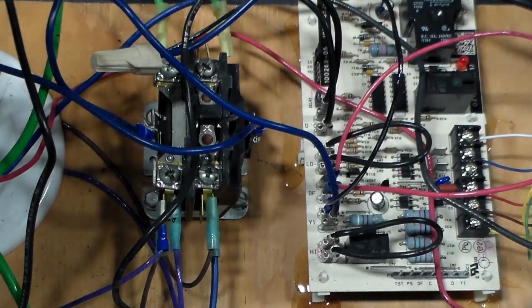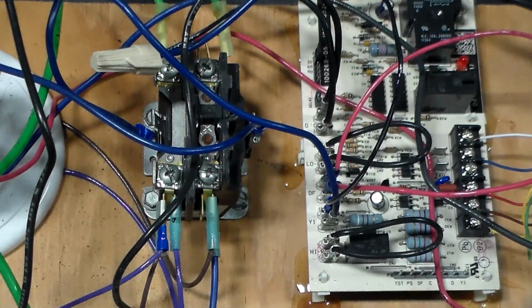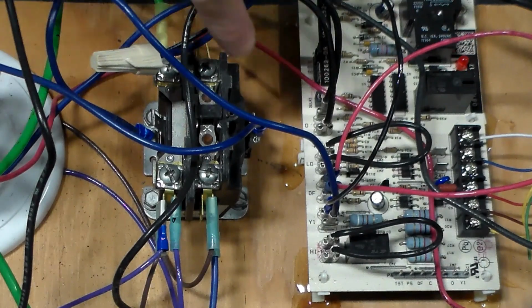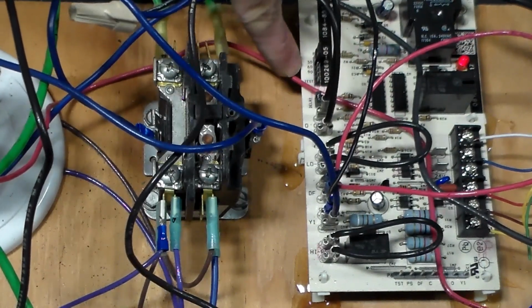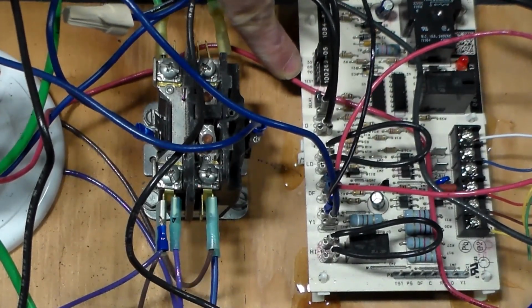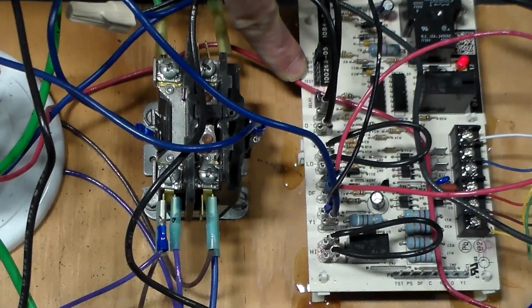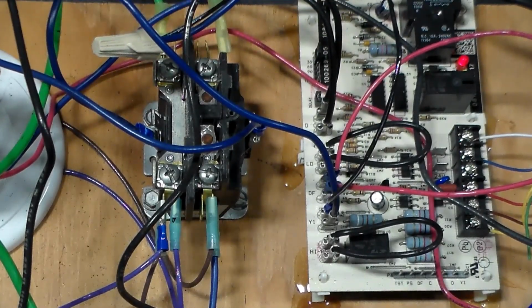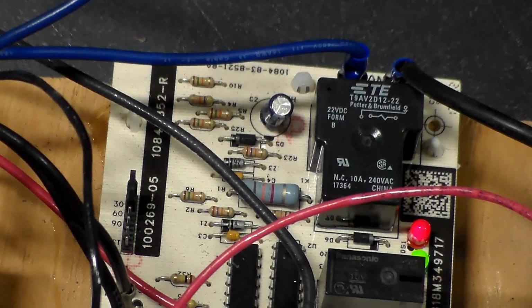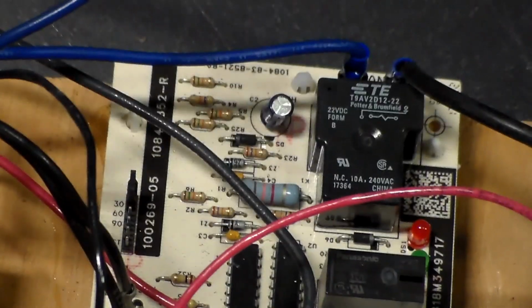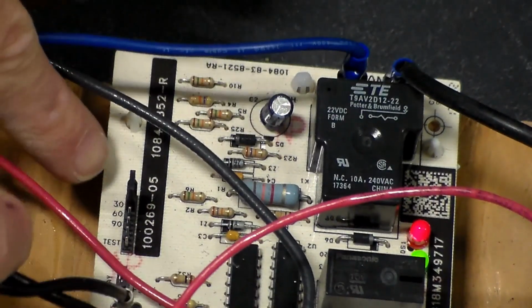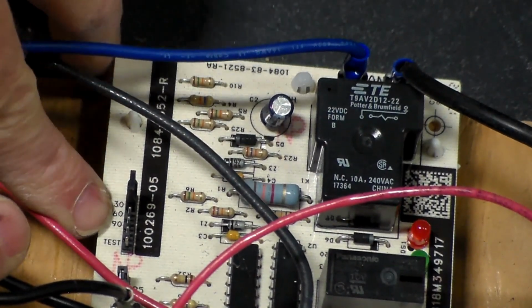So we'll talk about some more functionalities in a minute, and then we'll go through how defrost works and what these settings are about. Like this jumper pin over here, that's your defrost run time, but it's also got your test terminal over here. It's how we put it in test mode. So let's zoom back out so we can run it through some basic operation here. You know what? I think we should talk about this first. This jumper pin down here, it says 30, 60, 90, and test.